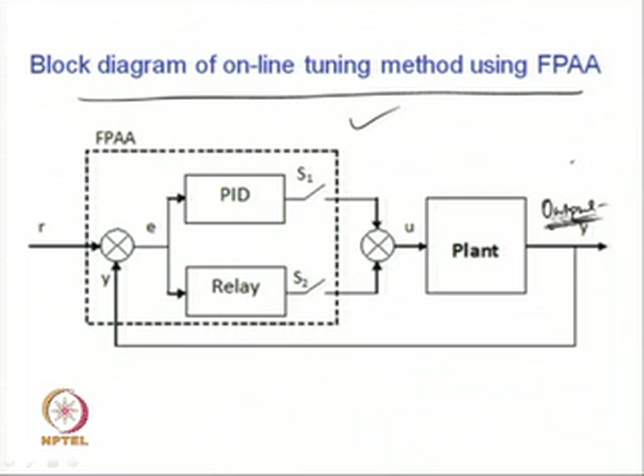Okay. Now, go to the decision block and check for any change in the output. Particularly when this tuning is initiated, the system output will be tracked continuously by the FPAA, and as and when the output increases or decreases above or below a certain threshold value, the auto tuning is invoked. Okay, the relay is invoked and then the auto tuning process starts, and the updation of PID parameters is carried out till the output is acceptable to you.